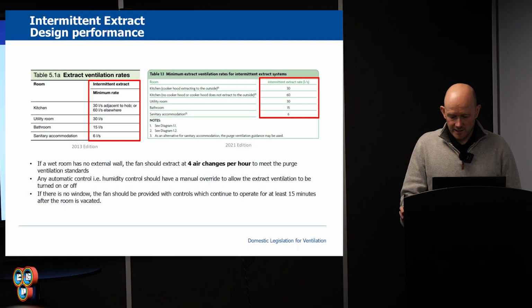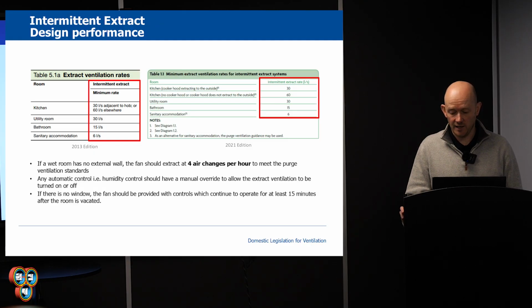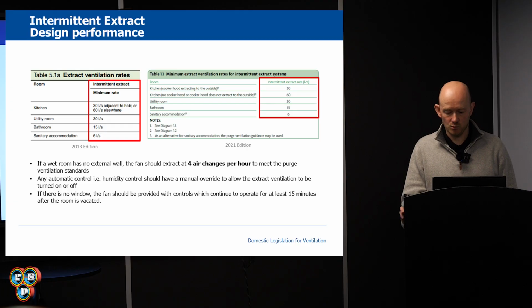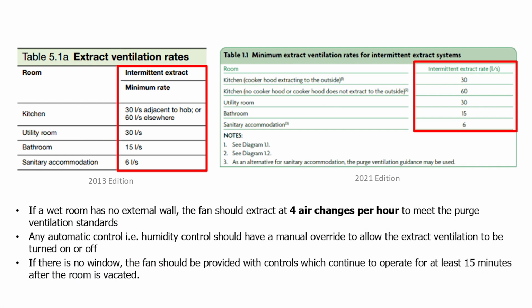Extract rates are unchanged, but there are key points to be aware of. If a wet room has no external wall, the fan should extract up to 4 air changes per hour in order to meet the purge ventilation standards. It should be noted that for larger wet rooms, this may exceed the minimum extract rate. For example, an internal bathroom of 15 metres squared would need a minimum intermittent rate of 16.7 litres a second. So because of the nature of the room, it exceeds what Part F is asking.